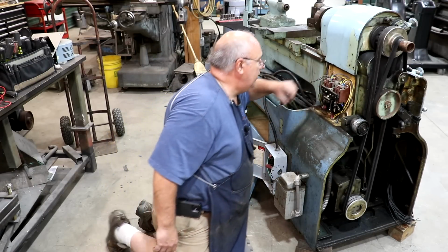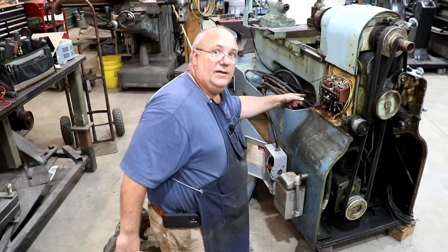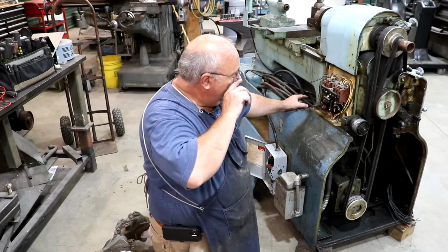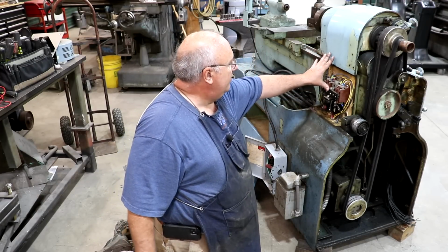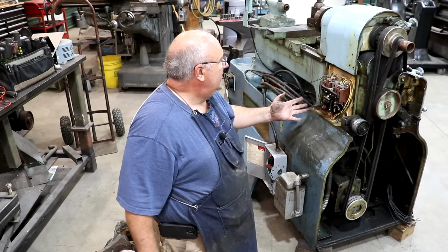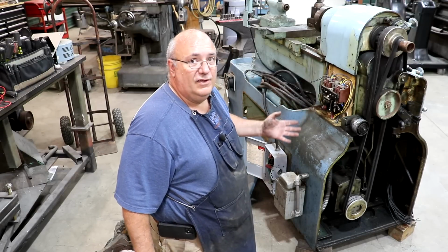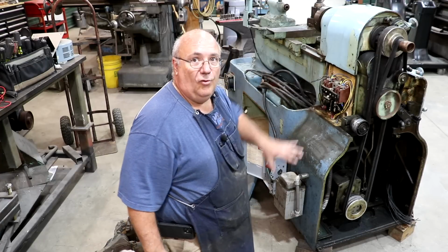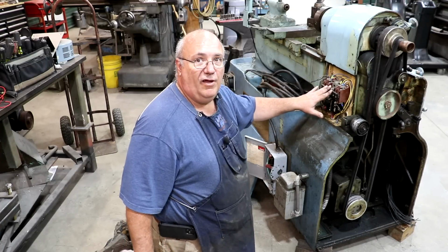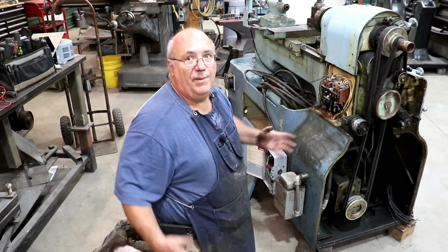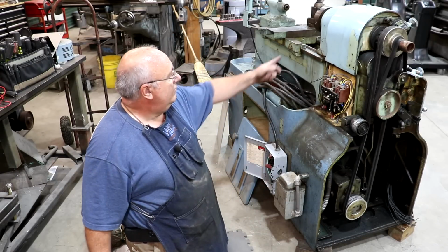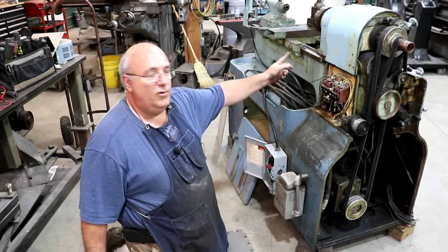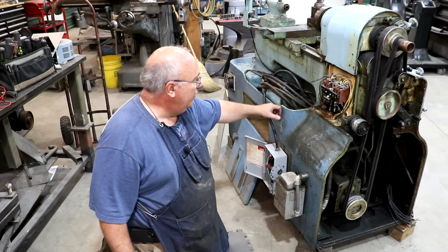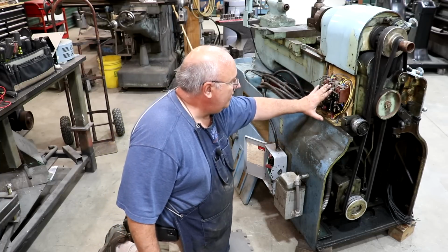This contactor up here, whenever you hit the main on-off button over there, would engage this contactor, and all it did was give power to the whole system. So this is kind of the master on and off. When you turn this on, you're just turning the power onto the machine. Then whenever you move the switch up front, forward and reverse, that's what would engage the motor and all that kind of stuff. This is coming out.